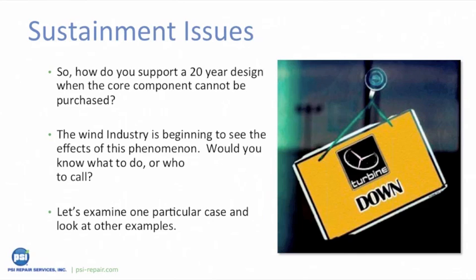There are many reasons the OEM is not meeting your expectations: they may no longer be in business, the wind regime in the United States is fairly dynamic and caused problems with original turbine designs, or the design didn't match the application — shock, vibration, and harsh environmental elements are all factors. For electronics specifically, the largest enemy is too much heat, which is a very common problem in wind turbine situations.